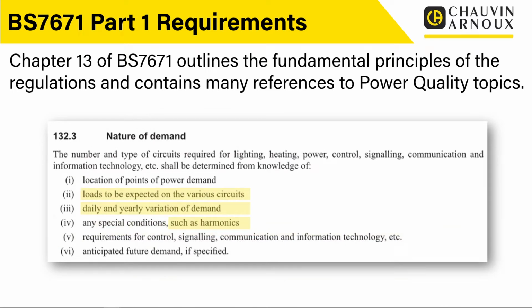Nature of demand. Nature of demand talks about the number and type of circuits that we have, and that we have to think about the demand so that we can set up the number and type of circuits in the installation correctly. And again, we mentioned things like the loads expected on various circuits, so we might need to do a load survey. Daily and yearly variations in demand. So again, a load survey would plot the actual variations over a daily period or maybe even a yearly period. And it also mentions there any other special conditions such as harmonics.